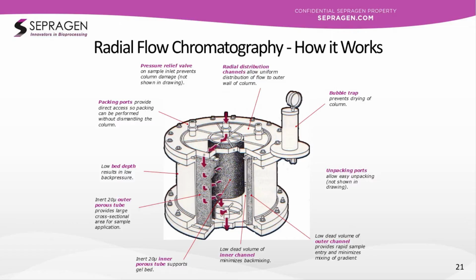And then in the center of the column, again, there's a cylindrical frit. So instead of a circular frit on the top and a circular frit on the bottom, as happens with conventional columns, here you have two cylindrical frits. And the resin is packed as a slurry into the space through these packing ports. And so in bigger columns, you have more packing ports, but you have a manifold, and through the manifold, you simply, once you've primed your column and filled it with buffer and driven all the air out, you simply pump in your slurry, and the slurry packs up in this intermediate space, and all the excess buffer gets squeezed out through the top or through the bottom.